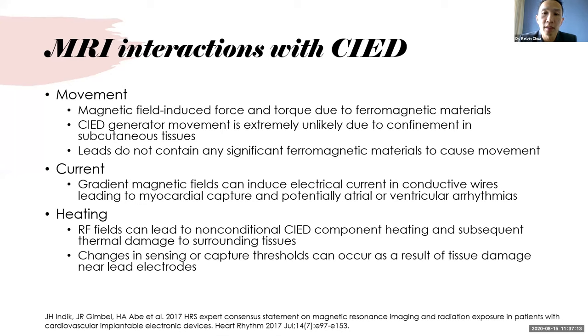Gradient magnetic fields can induce electrical current in conductive wires, leading to myocardial capture, and this can potentially lead to atrial or ventricular arrhythmias. Radiofrequency fields can also lead to non-conditional device component heating and subsequent thermal damage to surrounding tissues, much like a functional ablation. This local tissue thermal damage can also lead to changes in sensing or capture thresholds.